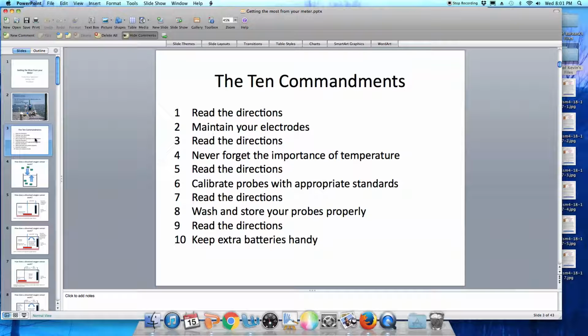Never forget the importance of temperature. The amount of dissolved oxygen in water, the conductivity measurements, and even the pH are temperature dependent. So your meter will be equipped with a temperature sensor. Make sure that temperature sensor is working correctly if you want to get the most accurate measurements. And of course, read the directions.